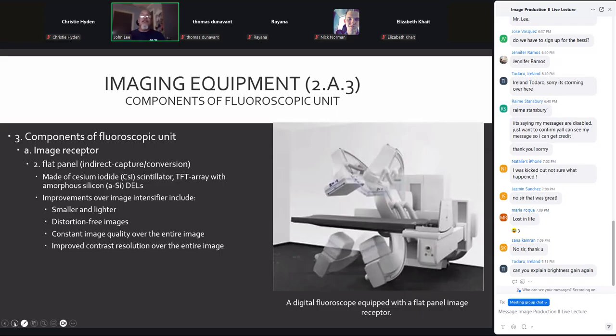If you don't have an image intensifier tube, you may have a flat panel detector or a CCD type detector. They can be indirect capture, they can be direct capture. The most affordable is going to be the indirect capture, and that's why it's listed here. The indirect capture, if you'll recall, in our flat panels, takes X-rays, utilizes a scintillator to convert the X-rays to light, then the light stimulates the amorphous silicon in the flat panel. That gives off the electric signal.